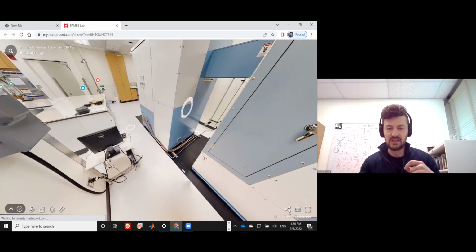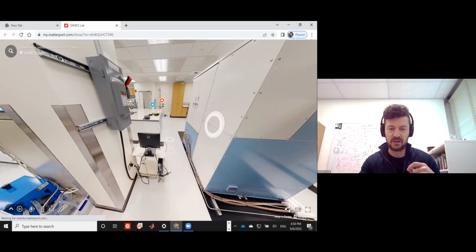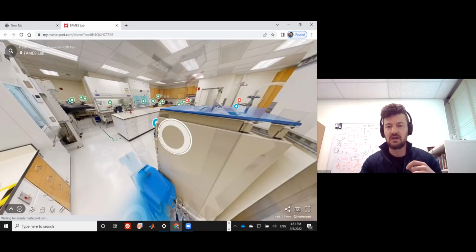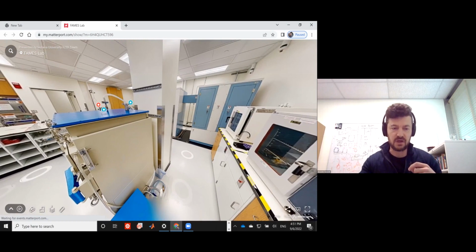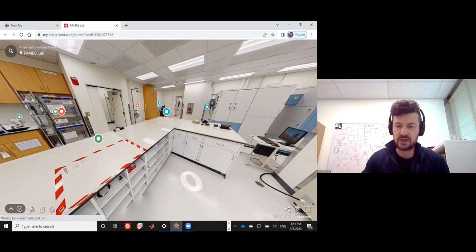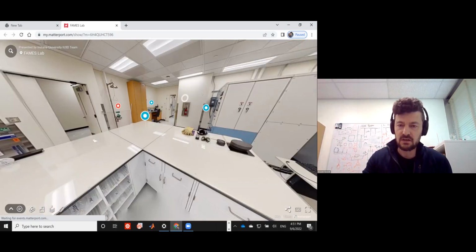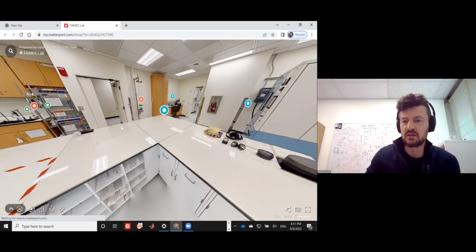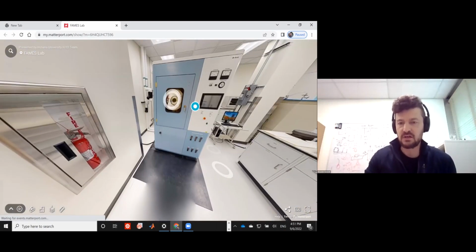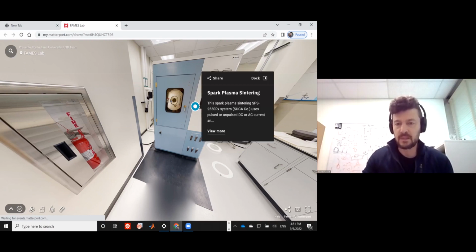So that system, for instance, has two feeds. One is 3-phase 480 that feeds the power supply, and another one is 3-phase 208, which controls the hydraulic press and the controls. So you have here the chamber of the hydraulic press, vacuum controls, water manifold, so you have internally cooling water flow and gas flow.